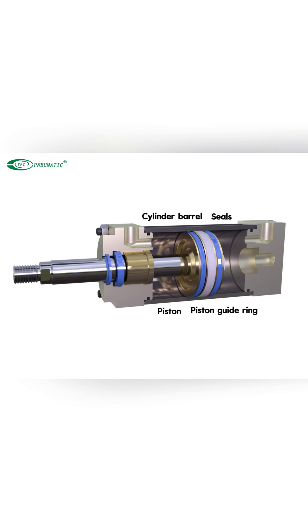If the adjustable cushioning screw is loosened during transportation of the cylinder with cushioning, adjust the cushioning to a minimum during trial operation. Gradually loosen the cushioning screw until satisfactory results are achieved to avoid excessive impact damage to the cylinder.